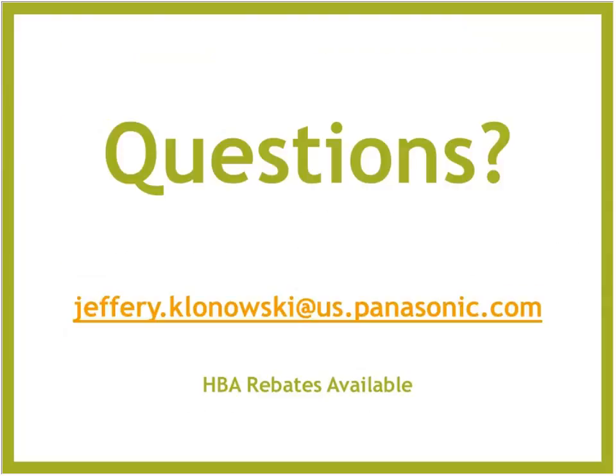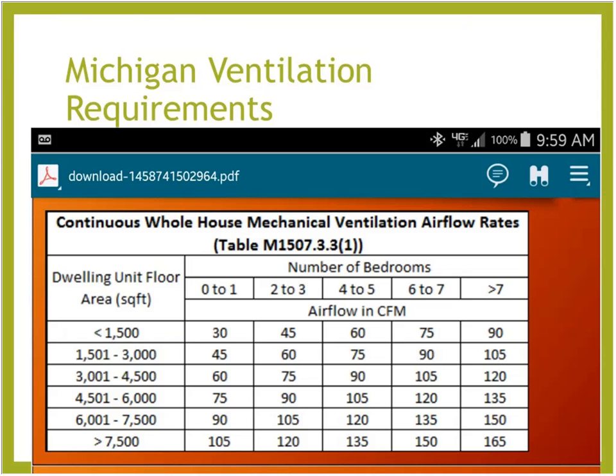Jeff, I'd like you to touch on the fan efficacy requirements of MUEC 2015 for ventilation fans, which would include bathrooms, kitchens, inline fans, and ERVs, HRVs. Well, Mike, I'm going to have to kick that back to you because I'm not as familiar with the efficacy requirements, unless maybe when you start talking about it, I'll get what you're talking about. All right, that's fine. The code requires for fan efficacy that you have 2.8 CFM of flow per watt, and that is on bathrooms and kitchens and ERVs and HRVs, and 1.4 CFM per watt on inline ventilation.